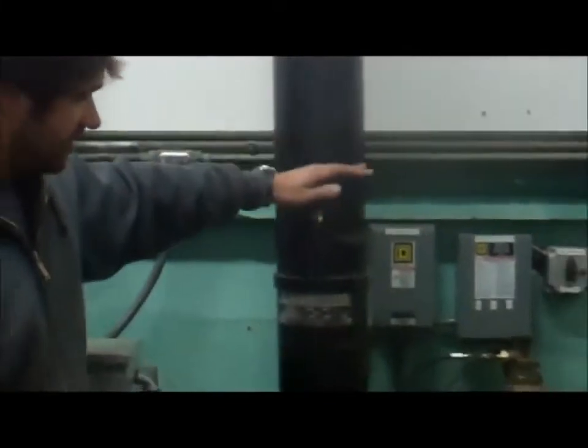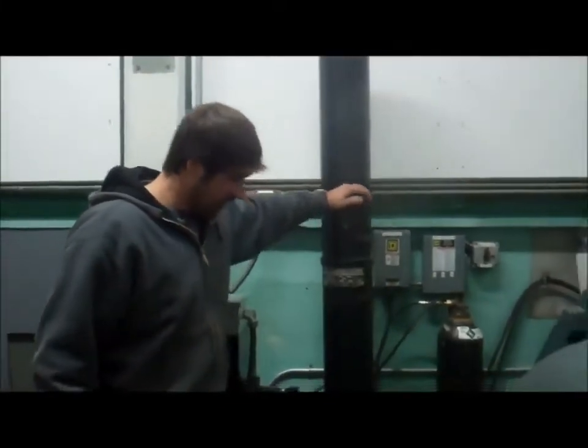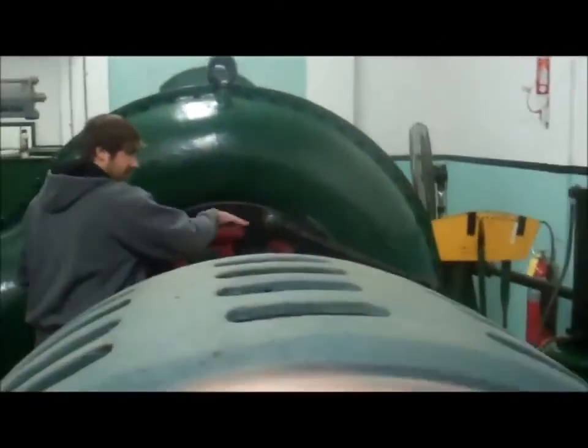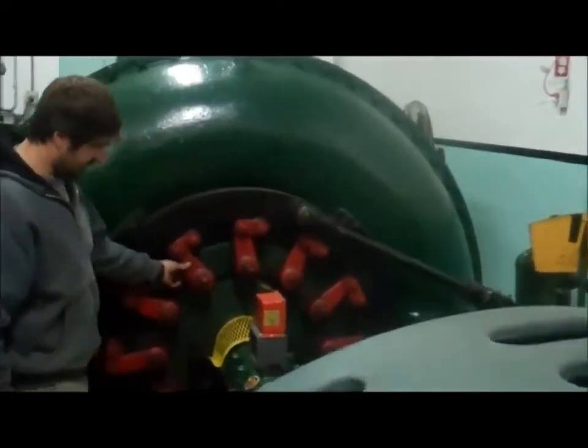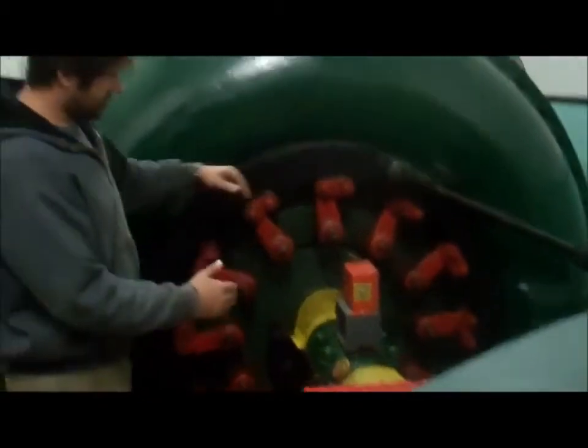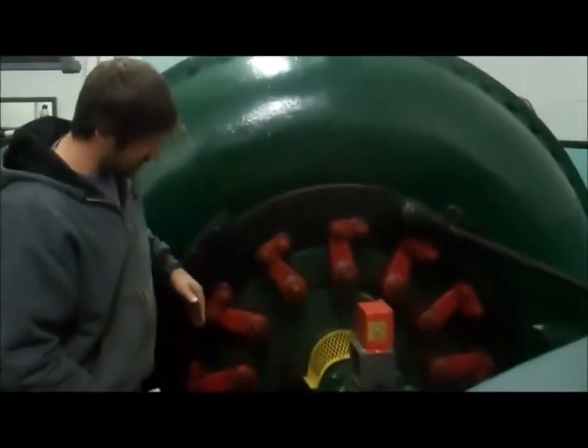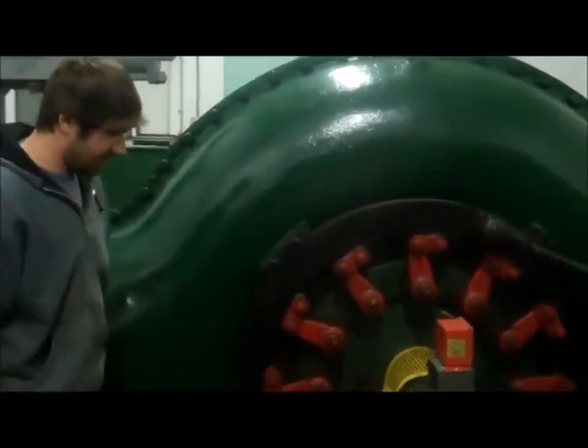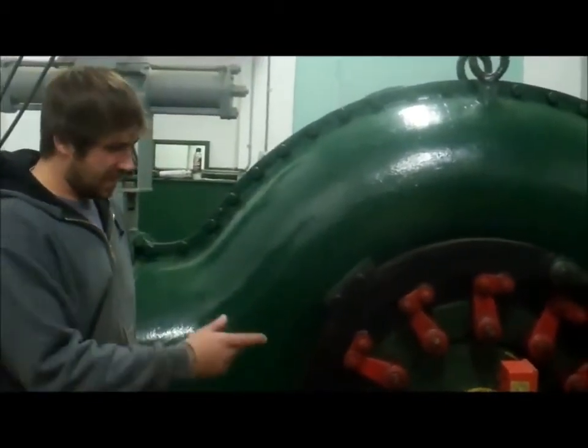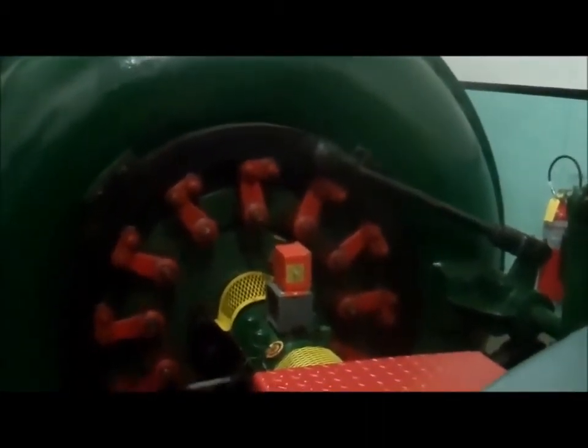And this is the same thing with the accumulator. This is the hydraulic accumulator. It's pressurized nitrogen with hydraulic control. So if we lose power, we still have hydraulic controls to the machine. And it's got the same setup as number 3, where this whole wheel spins like that, which simultaneously adjusts all the gates in there. There's fins on the inside of each one of these linkages, and they all spin together. And this is, again, babbitt bearing, no roller bearings, no moving parts, and that's why they last so long.